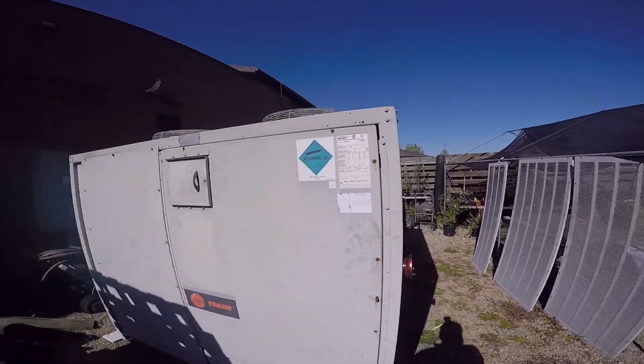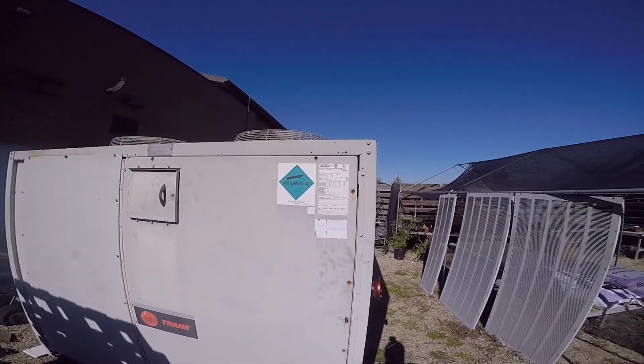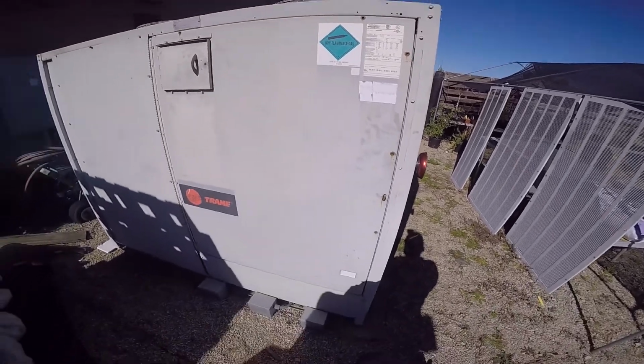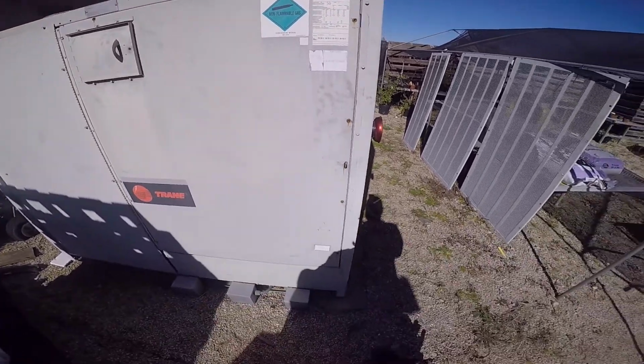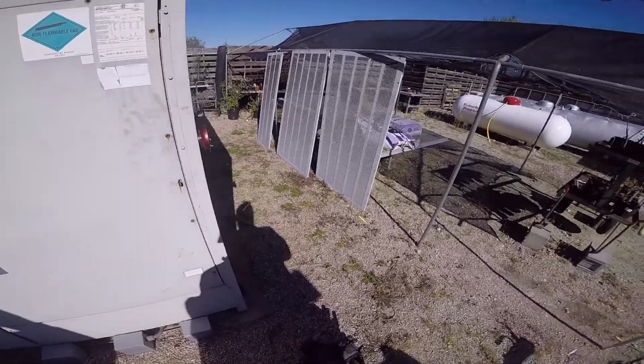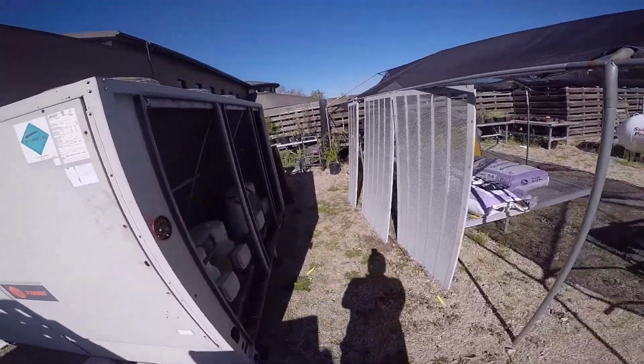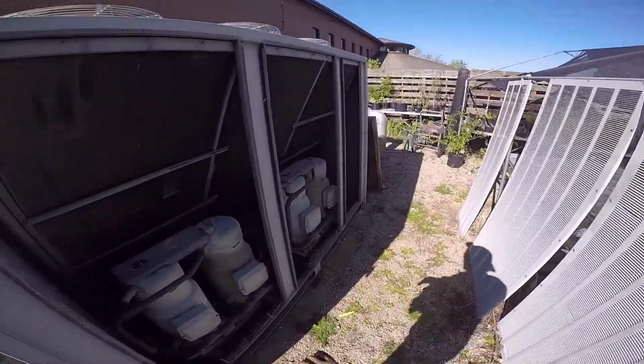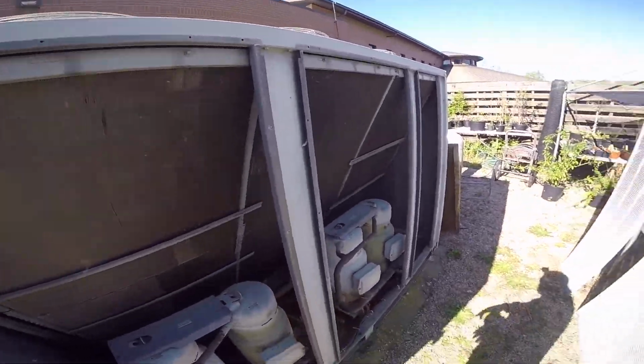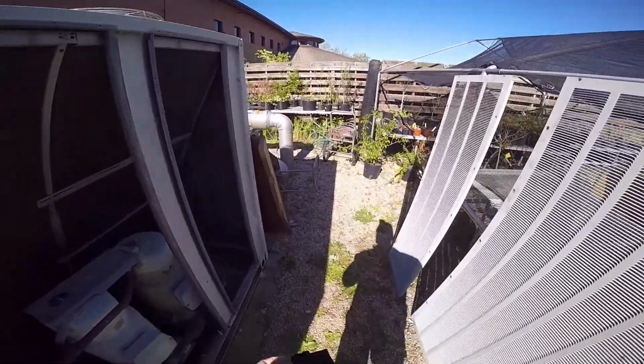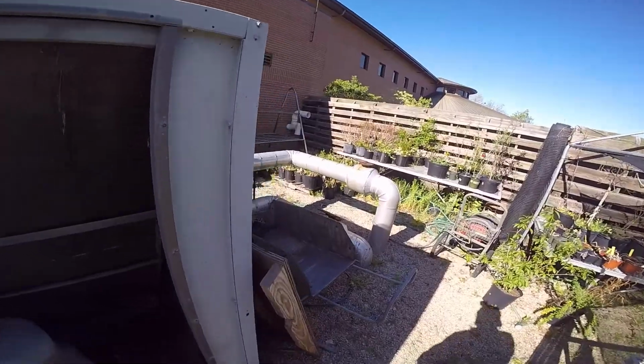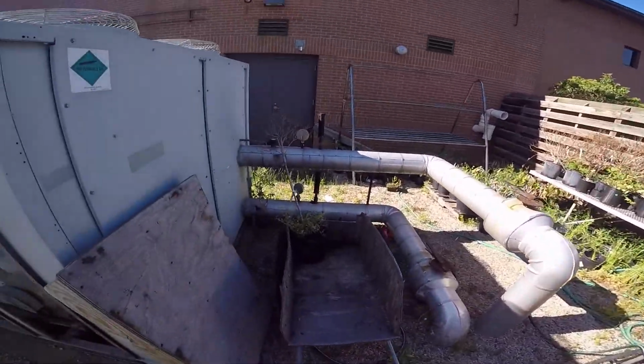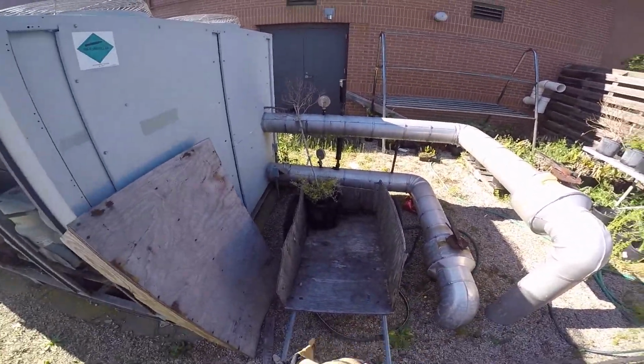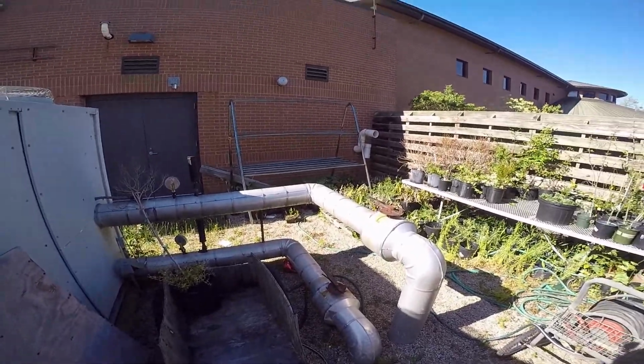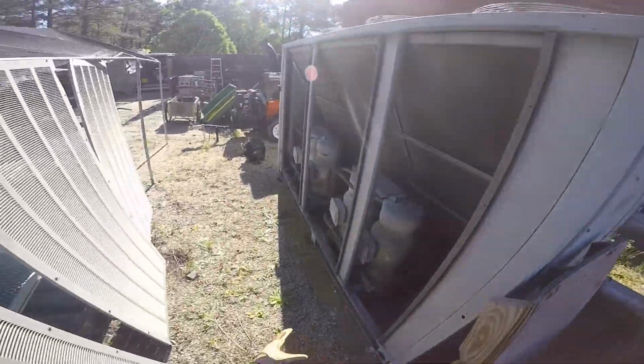All right, so we are now looking at a Trane CGAF air-cooled chiller. As you can see, air-cooled means we have condensers to transfer the heat outside, but we are still water-cooled. Here's our chill water loops from the building, and our pumps are in the mechanical room.